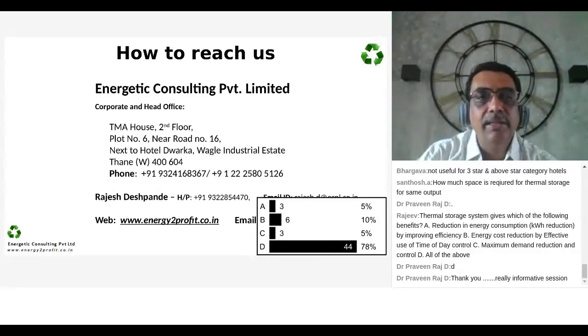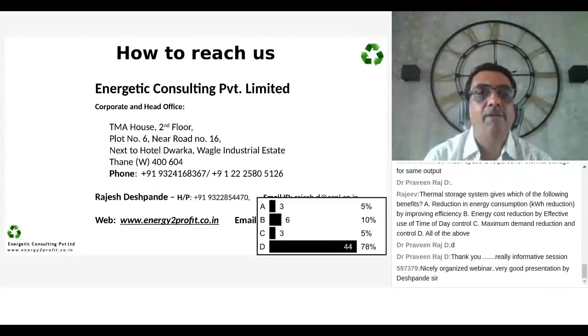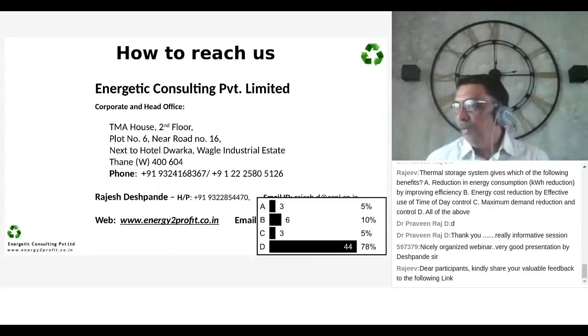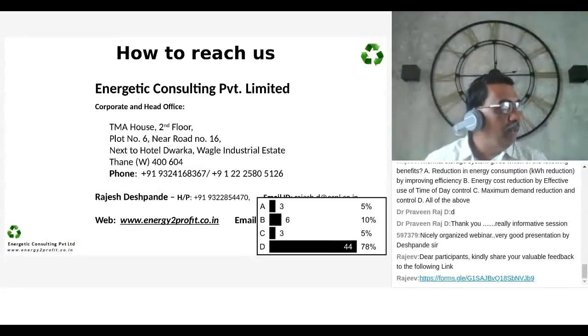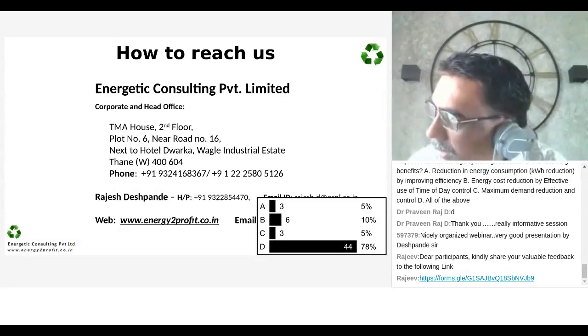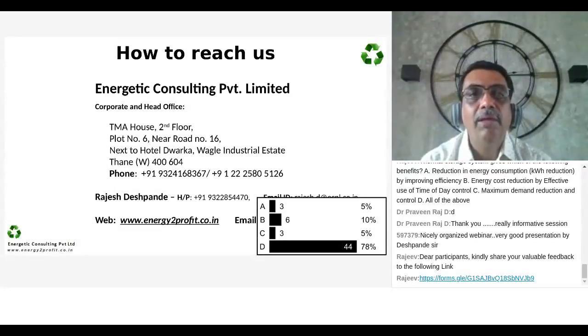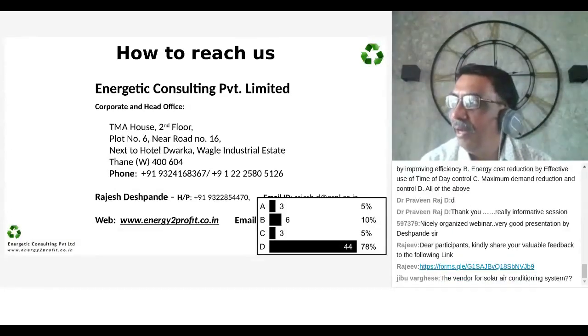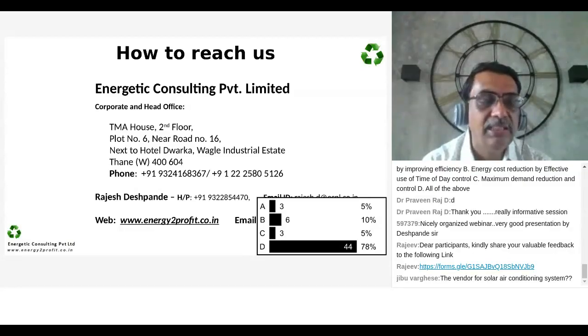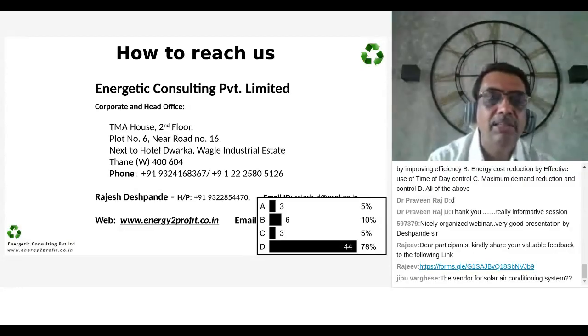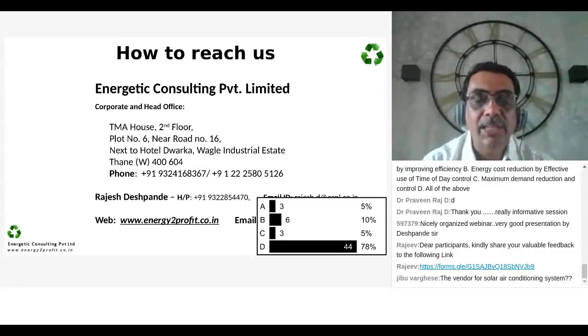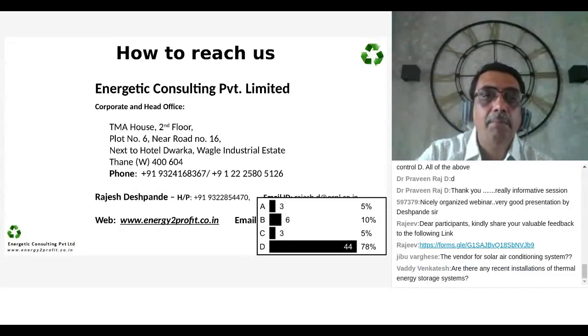I think I will just read through some of the questions here. How much space is required for thermal storage for the same output? Very difficult to say. It depends on size, but typically you have a 40 meter cube storage device, which gives you about 100 TR hours during the 8 hours charge. That is a very rule-of-thumb figure, not really correct for all applications. It depends a great deal on the charging and discharging cycle. If you have one-time charge and one-time discharge, then the size is bigger. If you have a simultaneous charging and discharging facility, that may be lower.